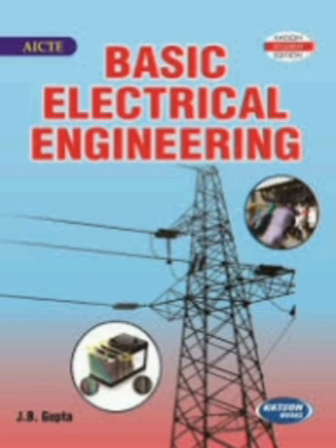The core of a transformer should have low reluctance and high permeability. It is made from CRGO, cold rolled grain oriented material, with 4% of silicon. It is laminated to reduce eddy current losses. Types of transformer construction: core type and shell type.